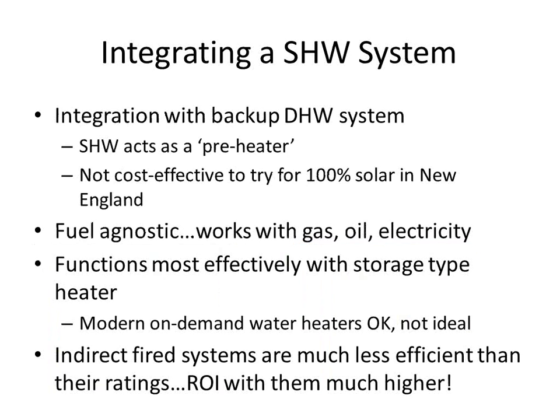Okay, so now that we know where to put the collectors, how do we integrate this system with your existing domestic hot water heater? As I said earlier, generally your solar hot water heater is going to act as a preheater. Cold water flows into your solar hot water storage tank, your solar system transfers heat to it from the glycol, and that storage tank gets hot, or at least warm in the middle of winter, then goes into your backup domestic hot water heating system, which delivers it to your house.